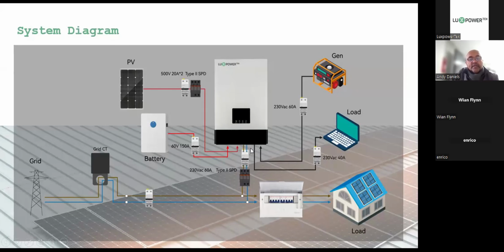So always be mindful of the fact that whatever load you connect on this side can exceed the capacity of the machine on bypass. But when it's inverting, in other words, when it's running in off-grid mode or supplying these loads from battery and PV, then the limitation will be 6 kilowatts. Okay, so there you've got your loads, your non-essentials, essentials, and your generator with the suitable circuit breakers connected.